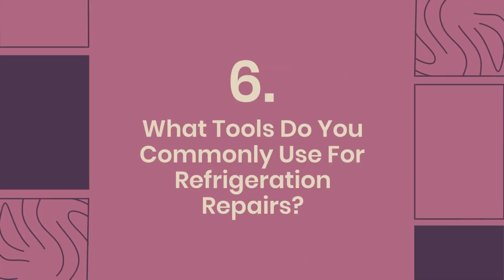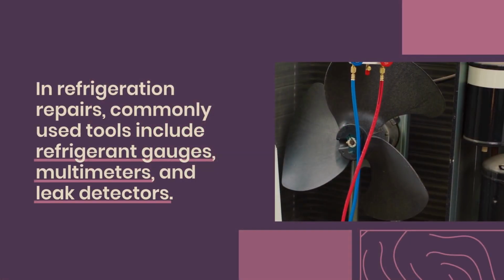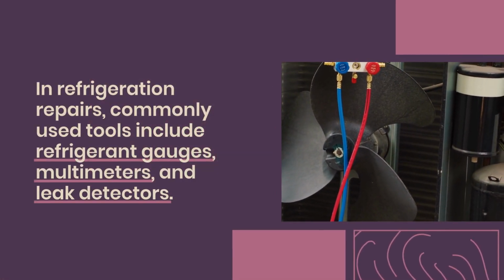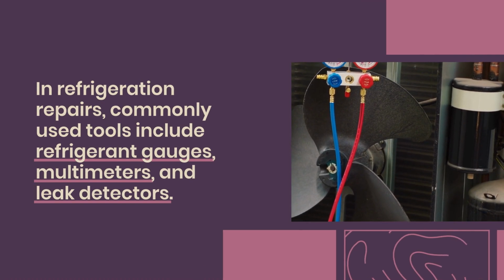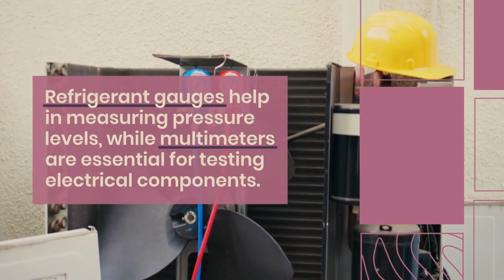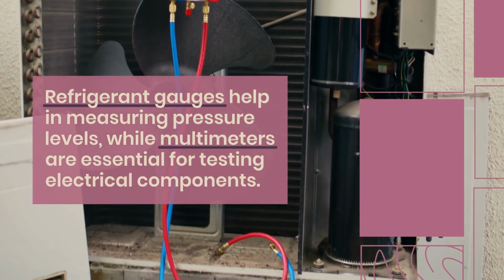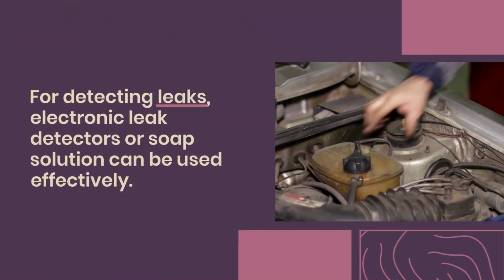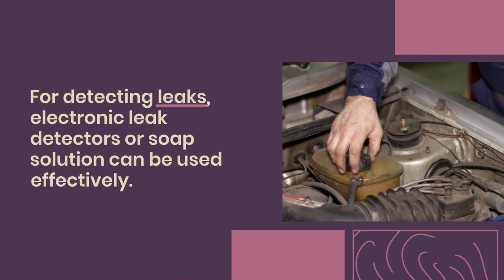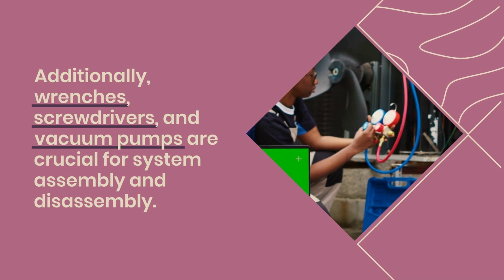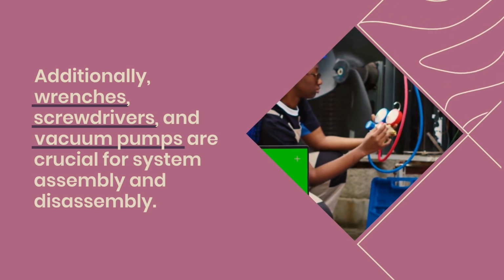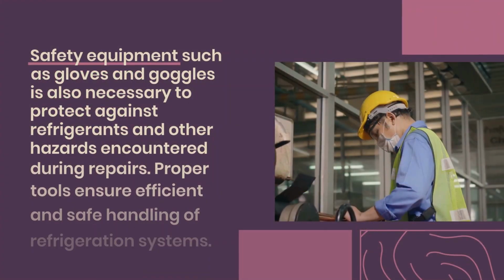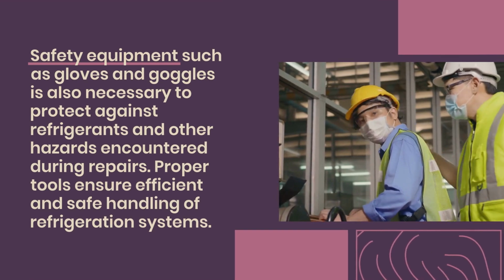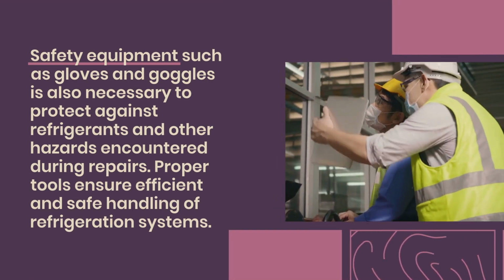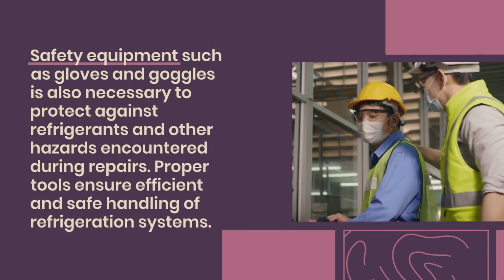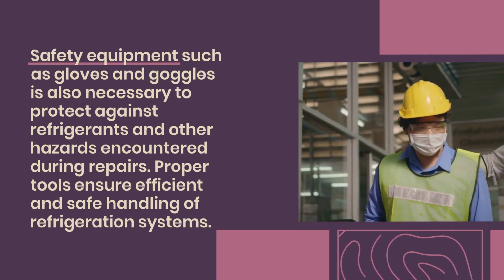6. What tools do you commonly use for refrigeration repairs? In refrigeration repairs, commonly used tools include refrigerant gauges, multimeters, and leak detectors. Refrigerant gauges help in measuring pressure levels, while multimeters are essential for testing electrical components. For detecting leaks, electronic leak detectors or soap solution can be used effectively. Additionally, wrenches, screwdrivers, and vacuum pumps are crucial for system assembly and disassembly. Safety equipment such as gloves and goggles is also necessary to protect against refrigerants and other hazards encountered during repairs. Proper tools ensure efficient and safe handling of refrigeration systems.